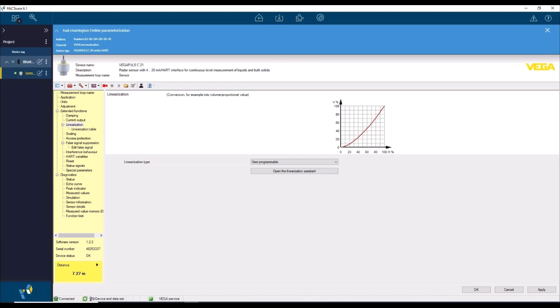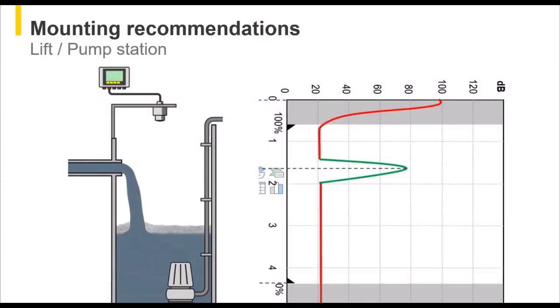All right, I'm going to take us back to the PowerPoint just for a moment here. Okay, so here we go. So now let's look at how to set it up. So here we go. This is going to be now for a lift station. When the sensor is installed, if at all possible, try to find an area where you're not going to hit the fill stream and you're going to try to miss that pump head down there. So we have a procedure for this.